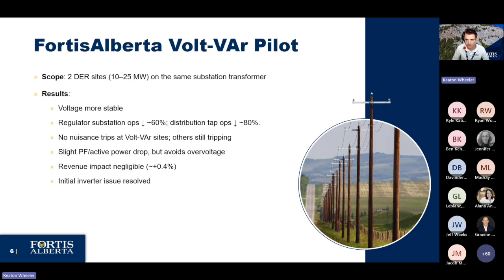First off, the voltage profile on the feeders where Volt-Var was enabled was significantly more stable. We saw substation regulator operations reduced by roughly 60% when the DERs were in Volt-Var, compared to the previous year when they were in constant power factor. Similarly, distribution tap operations were reduced by about 80%, a significant reduction. The sites with Volt-Var enabled haven't seen any nuisance trips since that control mode was enabled. Interestingly, on an adjacent feeder at the same substation but a different substation transformer, we're still seeing nuisance tripping problems for those sites, even though they're essentially at the same location—another reason why we're going down this path.